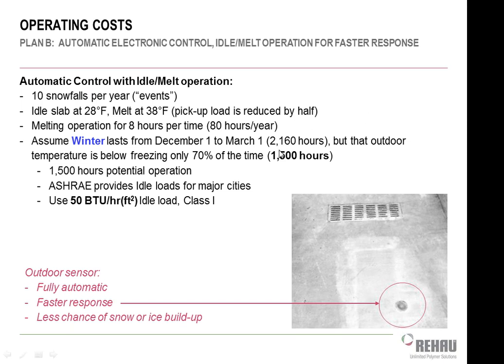So once again, 10 snowfall events a year. In this case, though, we're going to idle the slab at 28 degrees. So we're going to try to keep this slab fairly warm so we have less pickup time than if we just let it be the outdoor air temperature. But it's pretty easy to keep it at 28 degrees because we have very few hours in Illinois where we're under 30 degrees to begin with. It happens, obviously. It happens frequently, but it's not for a lot of hours.